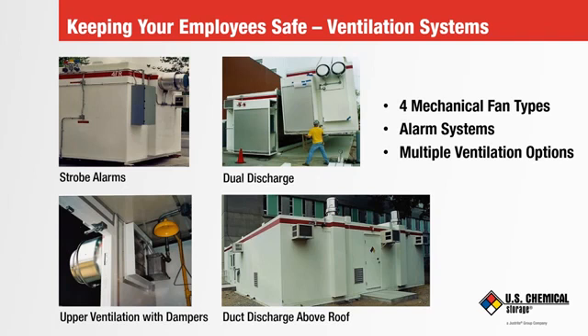Now here we have 4 photos. The one in the upper left-hand corner, there is a blue strobe on the roof edge for a fan malfunction alarm. The yellow strobe is for the sump spill alarm, and the red strobe for the fire alarm. There's also a single fan at the top of a single duct over a single exhaust vent. Then the photo on the right shows dual fans at the top of a dual duct over dual exhaust vents.